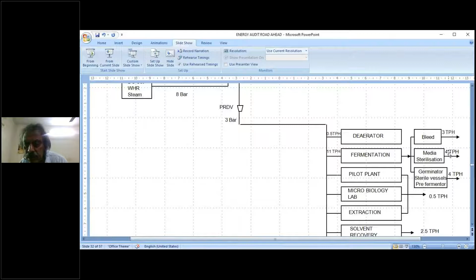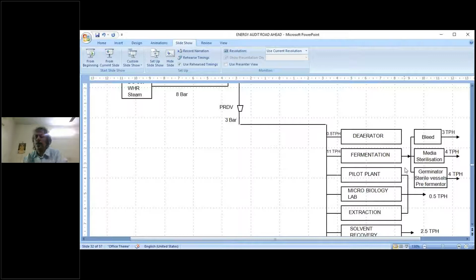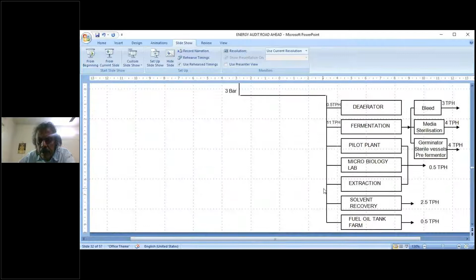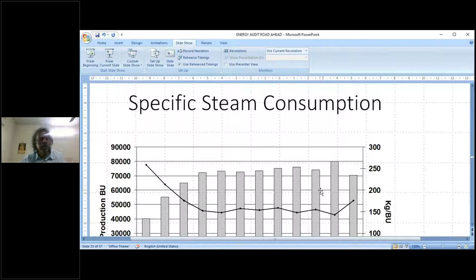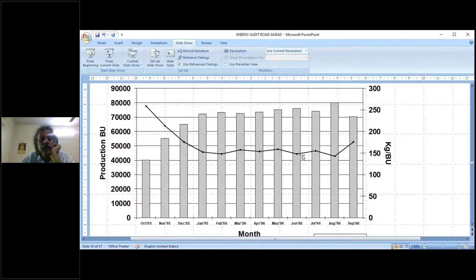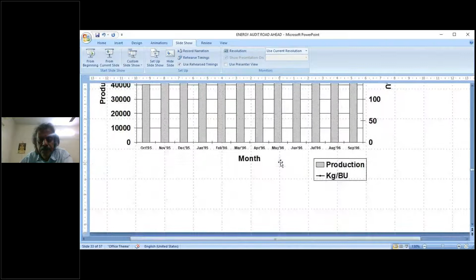When it's low pressure steam, what is the condensate coming out of each equipment? That is going to be the steam required. So you make a tentative steam balance. Some data is better than no data. Then you see the specific steam consumption per ton of product, how the steam is varying over the months. You ask why, how there is a variation. Again, these are all the data analytics which throw a lot of light on your energy use pattern.